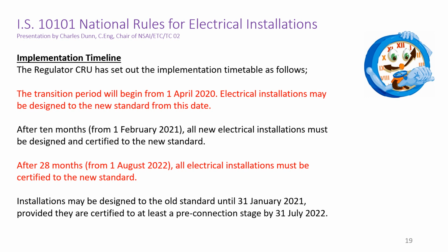The implementation plan for IS 10101 is as follows. The transition period will begin from the 1st of April 2020. Electrical installations may be designed to the new standard from this date. After 10 months, from the 1st of February 2021, all new electrical installations must be designed and certified to the new standard. After 28 months, from the 1st of August 2022, all electrical installations must be certified to the new standard. Installations may be designed to the old standard until the 31st of January 2021, provided they are certified to at least a pre-connection stage by the 31st of July 2022.